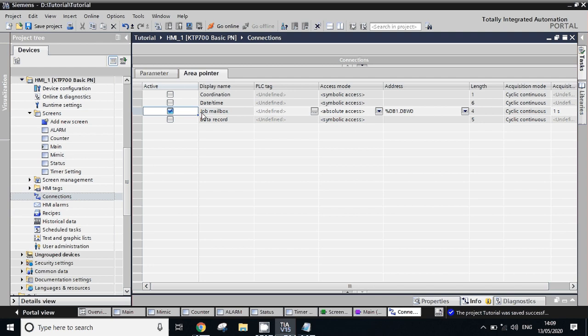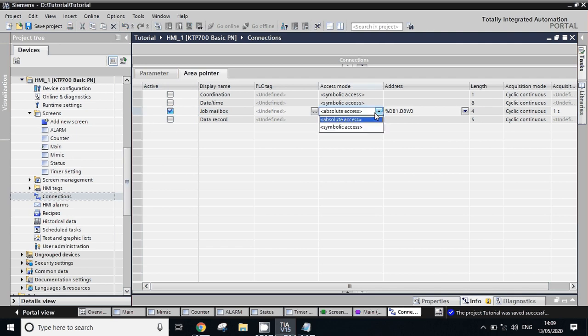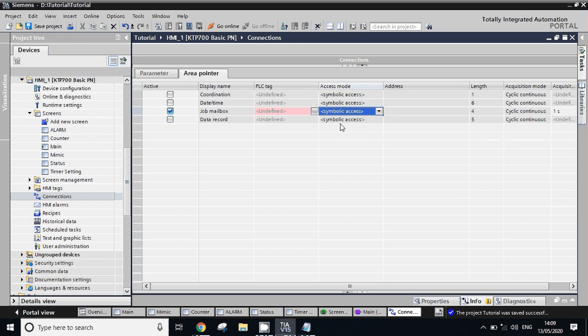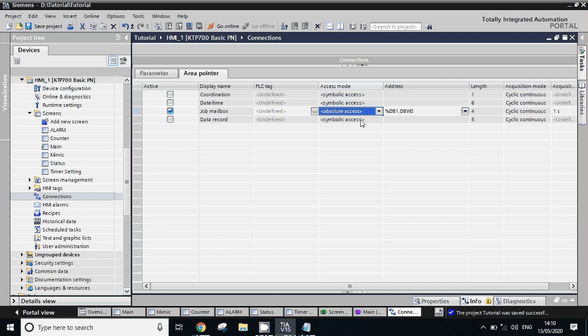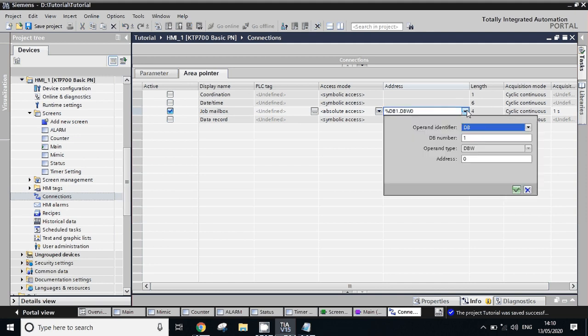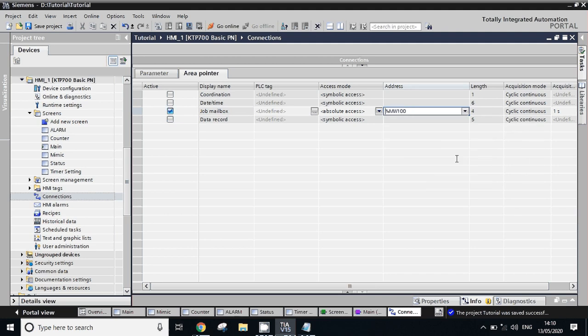Now in area pointer you have to check this job mailbox. Just check this, then here you have to select the absolute access. By default it would be symbolic access but you have to click on it and change to absolute access. And here we will take one tag, so we will take MW 100. So what you have to do: just check this, then select this as absolute access, give one address here - MW address.